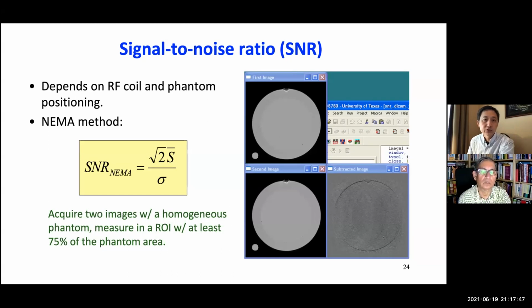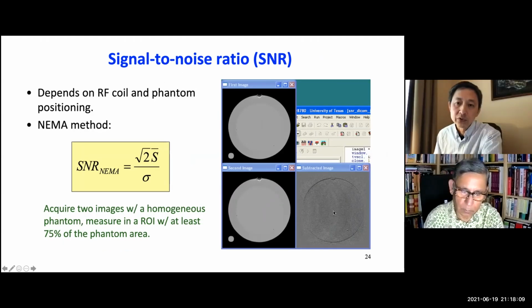There are many ways to measure signal to noise ratio. The most standard way is the NEMA method. The NEMA method requires two measurements, two scans. Like here, I'm showing you the first image and the first scan, and the second scan, using the same setup, same everything. And then you average them, and then you do a subtraction, okay?